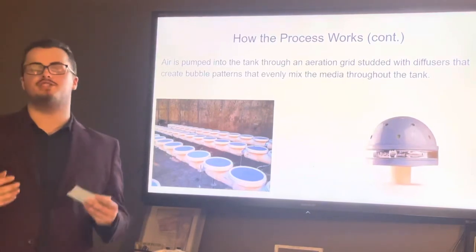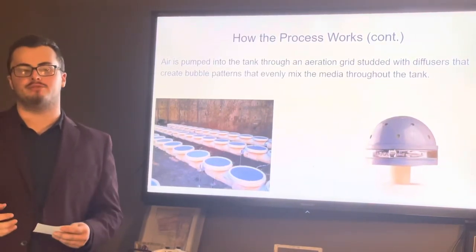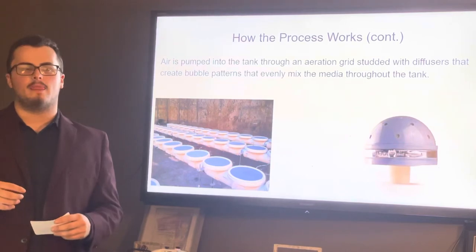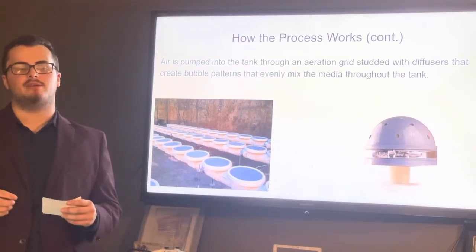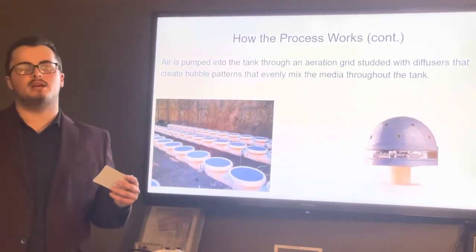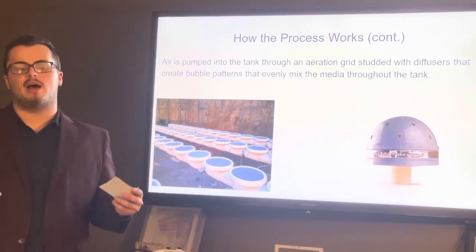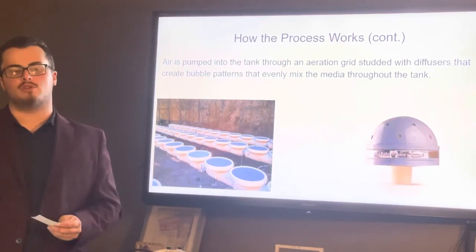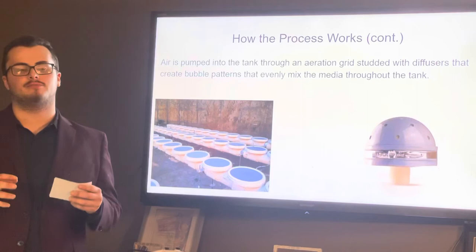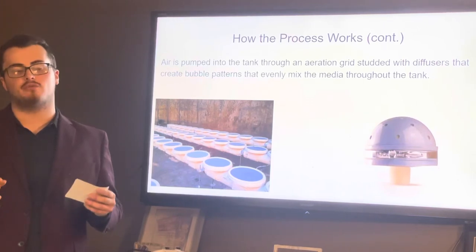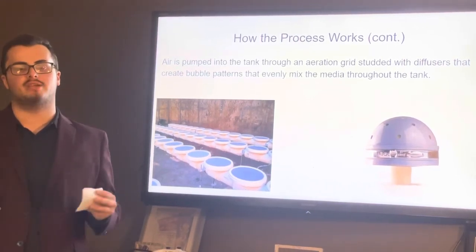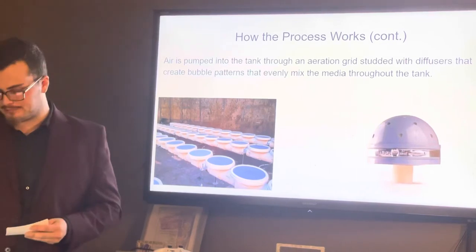Oxygen is supplied to the tank through a series of diffusers with small perforations of varying sizes depending on the project's needs, varying from fine to more coarse bubble depending on whether oxygen transfer efficiency or the actual mixing of the influent is more significant.